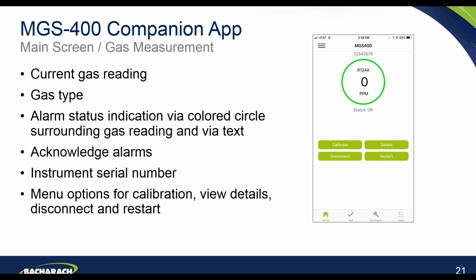So the main screen here will show the current gas reading, the gas type, and the alarm status indication. On the image on the right there, you see a green circle around the gas and ppm reading. If that detector was in an alarm, either a first or second stage alarm, that color ring would be either amber or red, and of course it would show the real-time ppm reading on there. You can utilize the app on this page to acknowledge alarms. So if there was an alarm condition and you had that set to be latching, you can acknowledge the alarm. It gives you details of the instrument serial number, and there are also a number of menu options that you can click through to for calibration, to view the details of the instrument, to disconnect from the Bluetooth, and to restart.